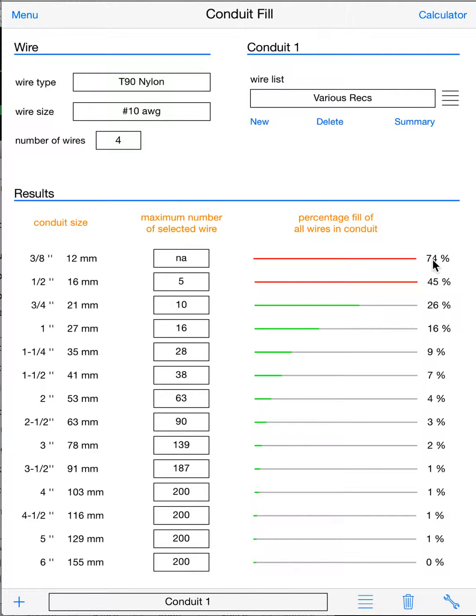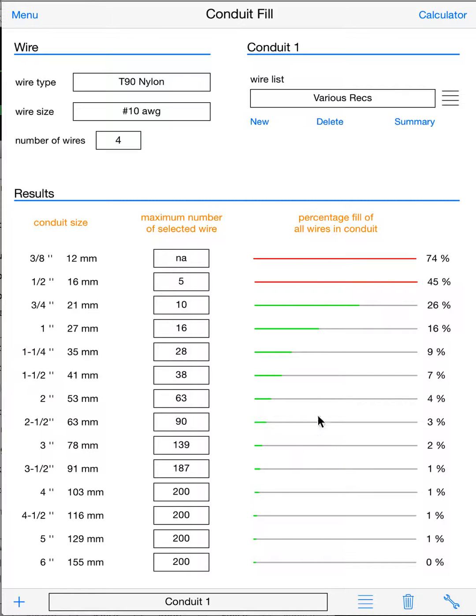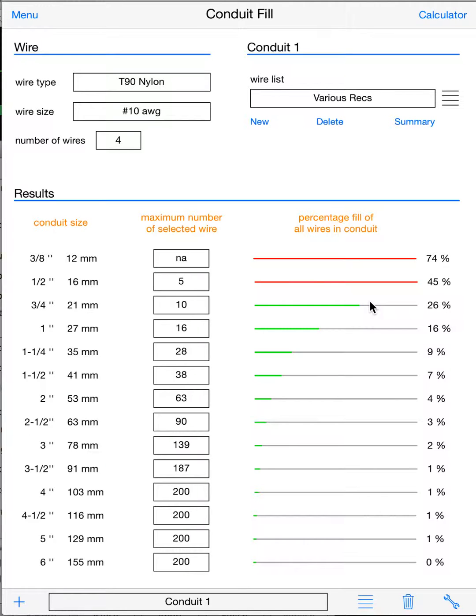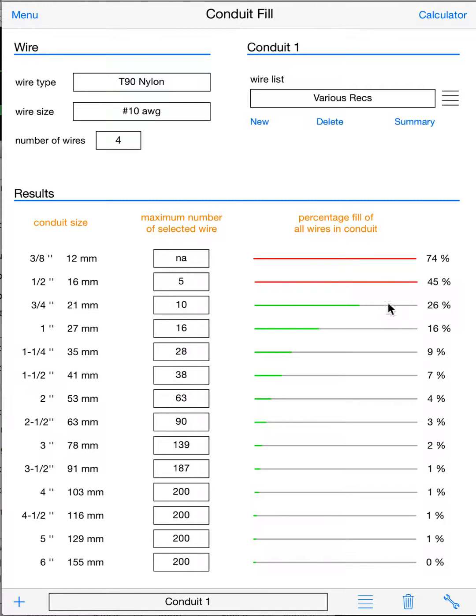And this is going to give how full each pipe is, and if it's red, it's going to indicate that it's overfull, and green is still underfilled according to the code. So this is showing 75% or 74% fill—it's too full. Half inch too full because our max fill is 40%, right, anything over two wires.